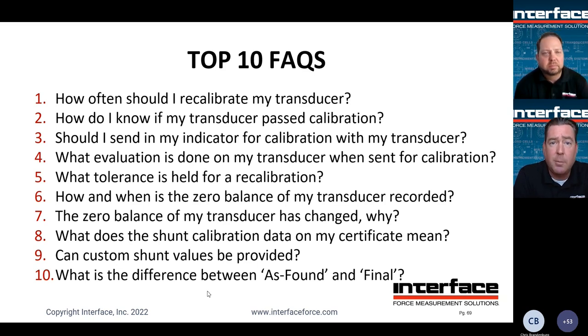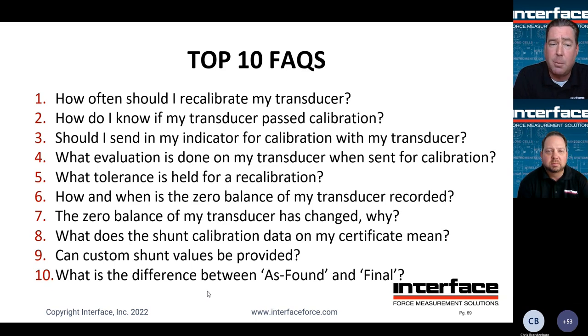Number 2, how do I know if my transducer passed calibration? Typically speaking, we've got an automated flag system in place with our calibration software. So if one of our load cells does not pass, it is flagged. And this is, of course, on the recalibration front. We don't ship transducers on the production side that don't meet spec. But if it does not pass recalibration per our specification, it is automatically flagged in the system and the customer is notified. At that point in time, it's customer choice whether or not they want to accept the transducer with calibration data as is. Number 3, should I send in my indicator for calibration with my transducer?